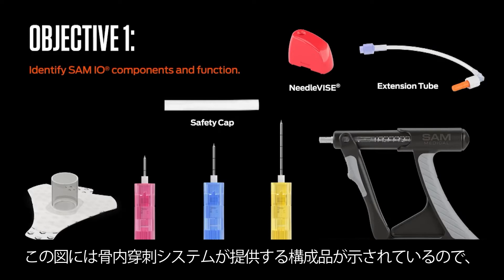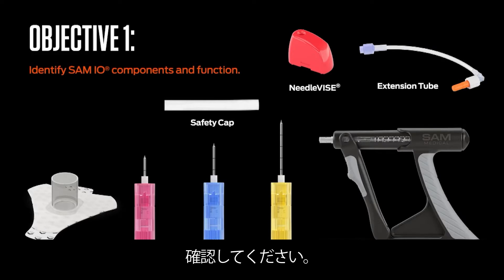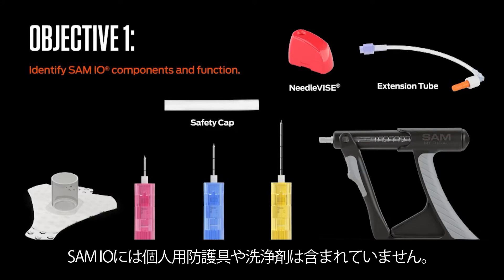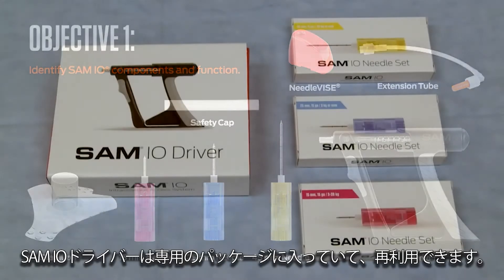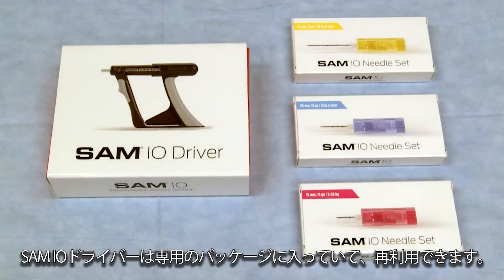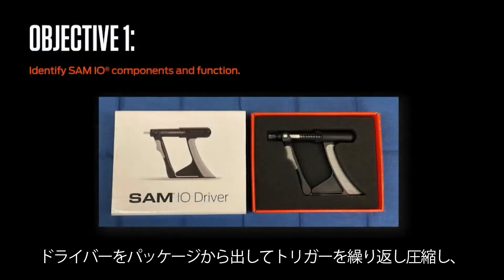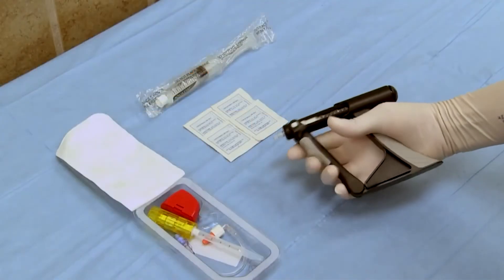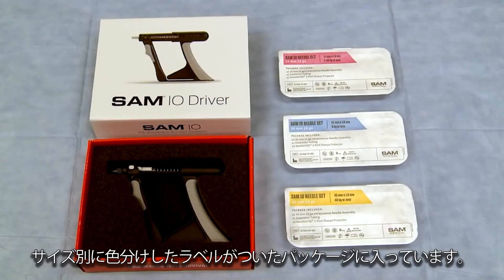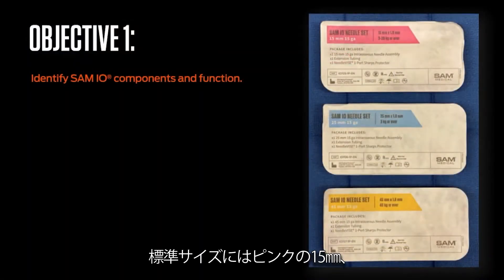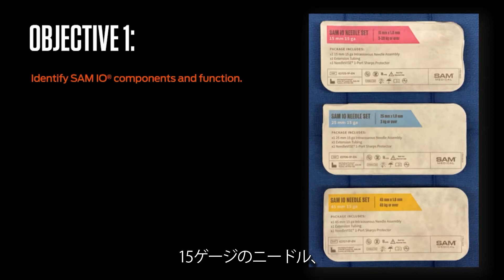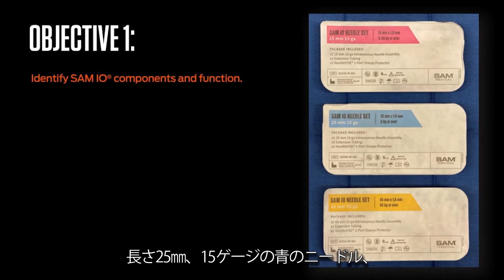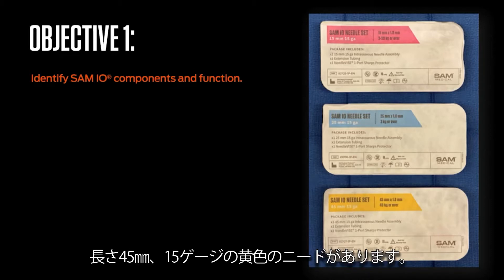Note the various components supplied by the IO access system are depicted in this illustration. No PPE or cleansing agent is supplied with the SAM-IO. The SAM-IO driver, which is reusable, can initially be found in its supplied packaging. Remove the driver from its packaging and repeatedly compress the driver's assembly to appreciate its unique function. SAM-IO needle assemblies are provided sterile in color-coded, size-specific, labeled packaging. Standard sizes include a pink 15 mm 15-gauge needle assembly, a blue 25 mm 15-gauge needle assembly, and a yellow 45 mm 15-gauge needle assembly.